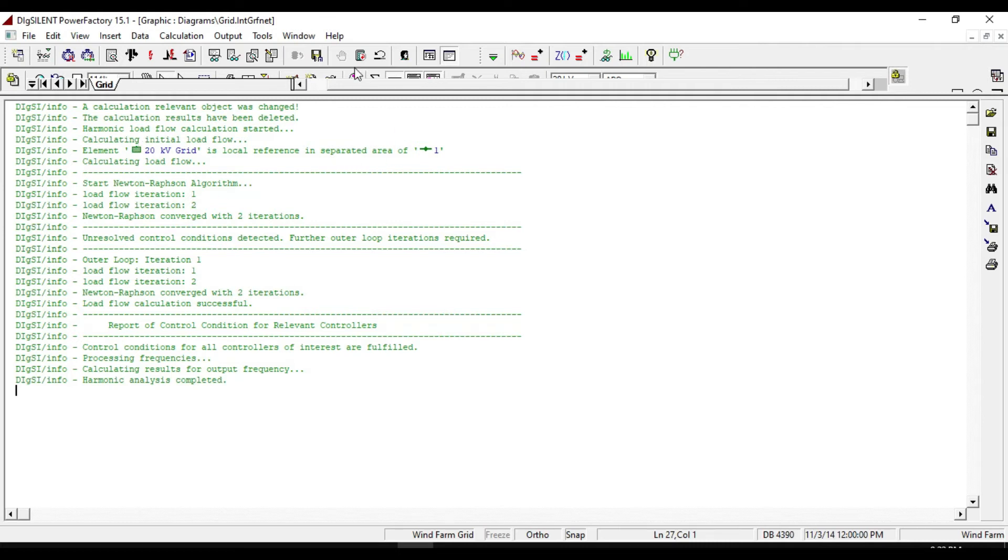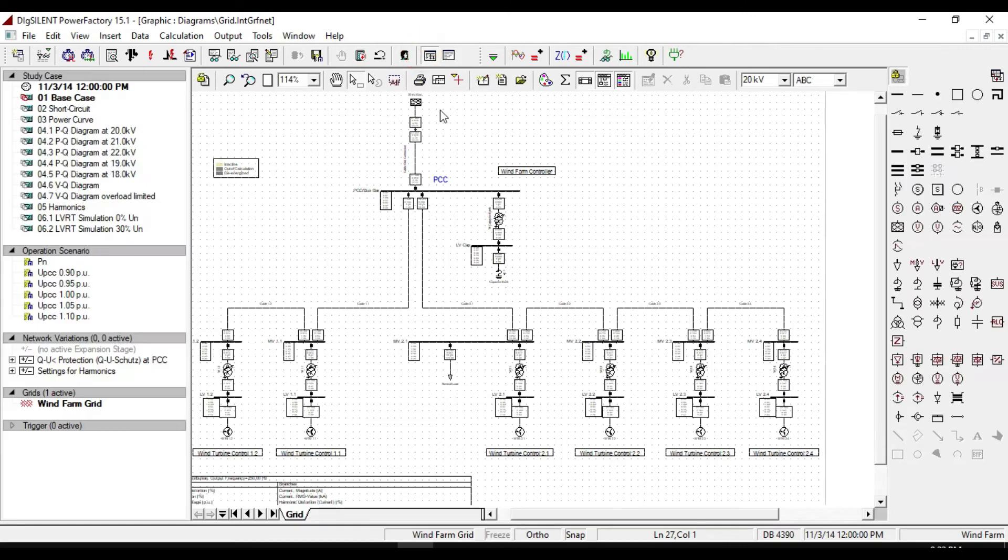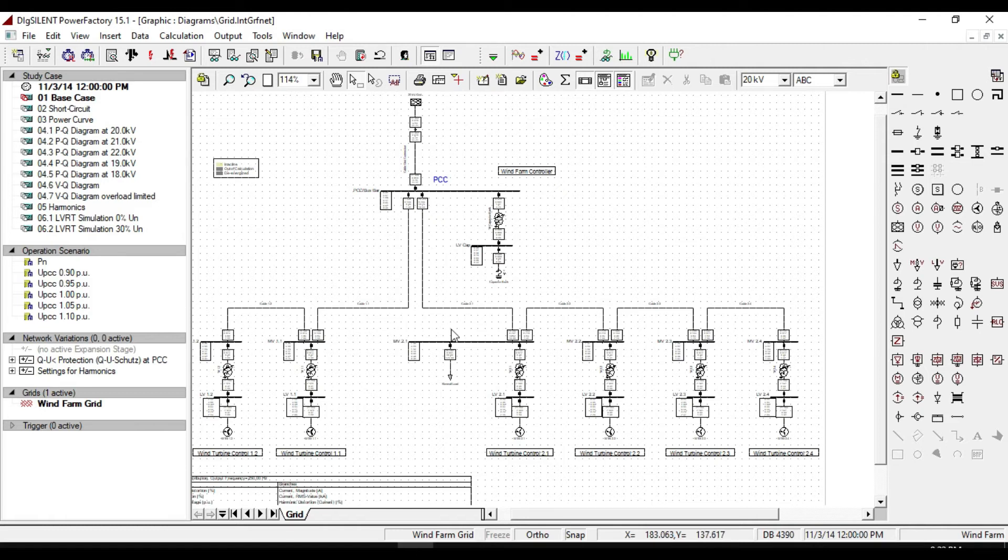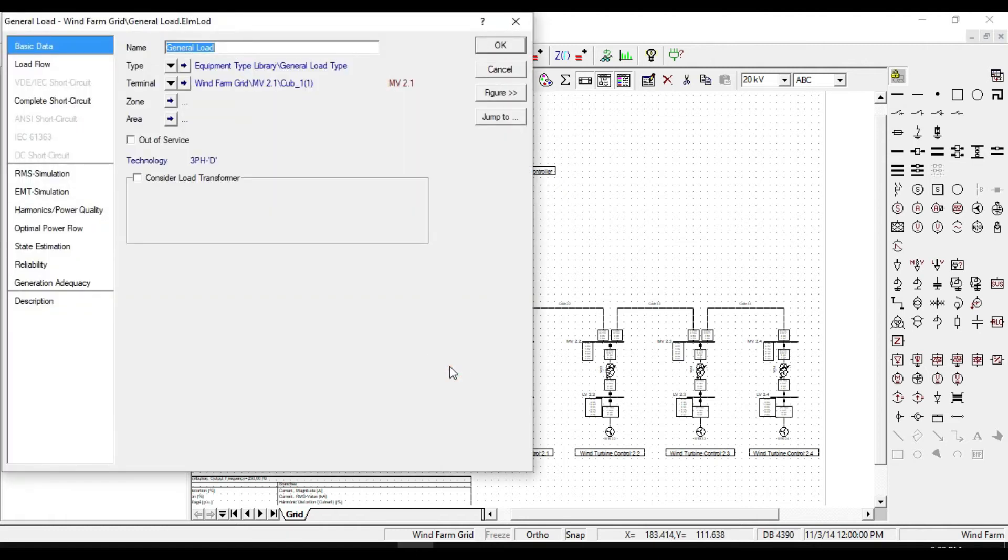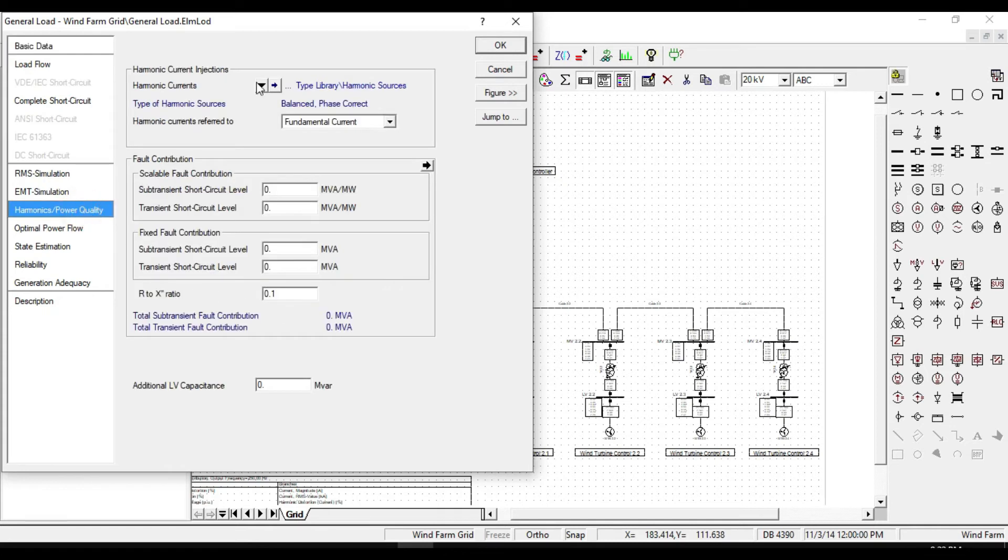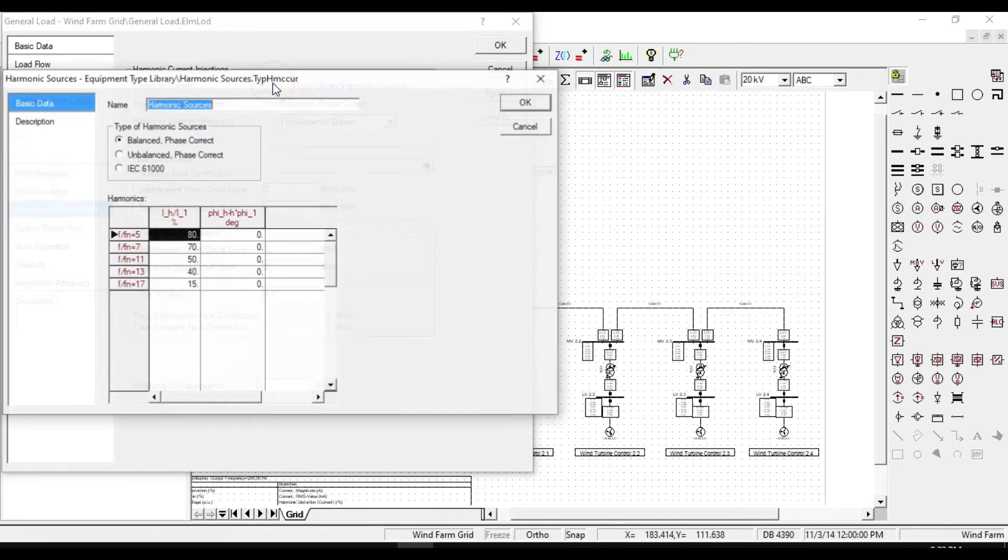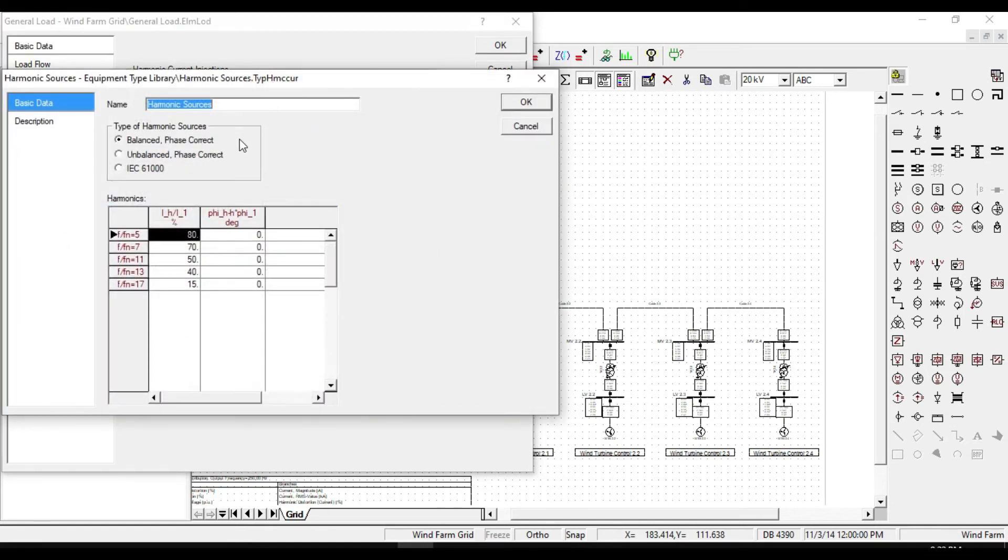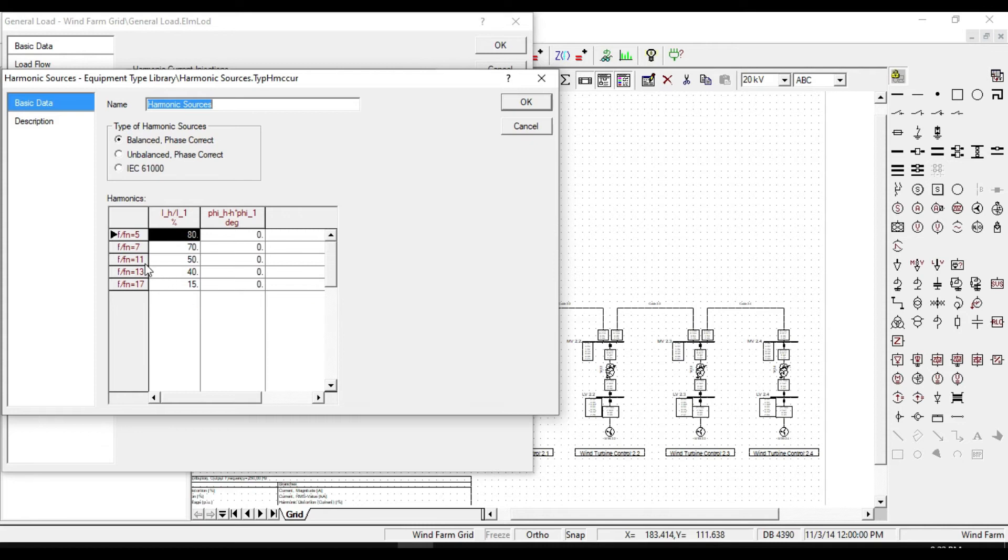One thing that I want to tell about loads before taking a look at the analysis of harmonic results: double click on the harmonic power quality. If you enter the harmonic current source, you will notice that the order of harmonics are defined as 5, 7, 11, 13, and 17, and there is not a third harmonic and also no even harmonics.